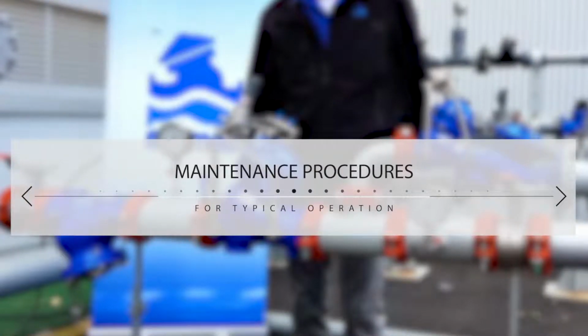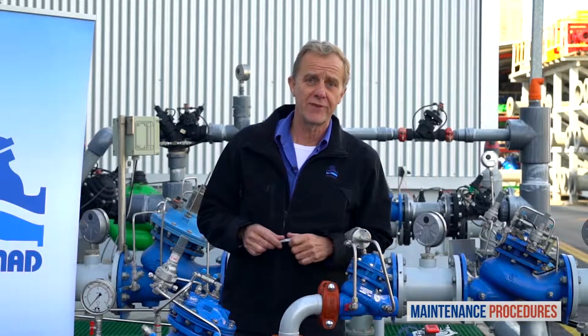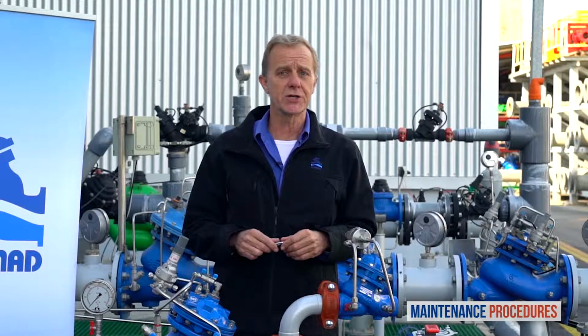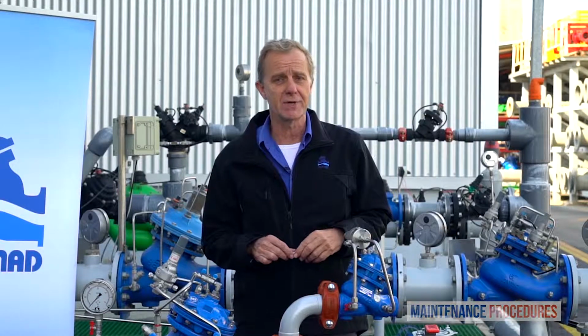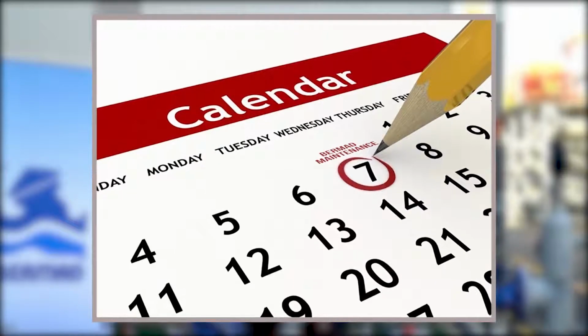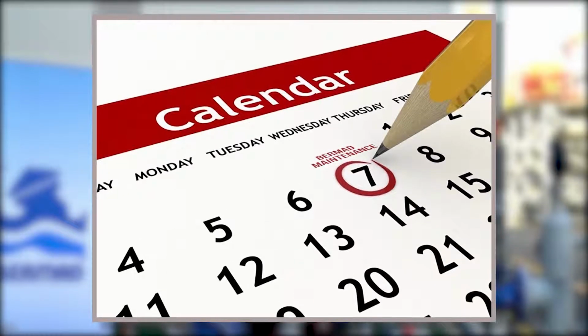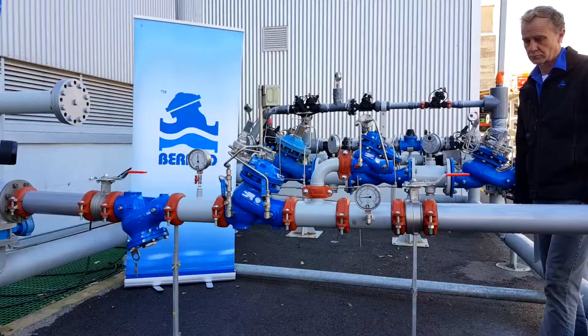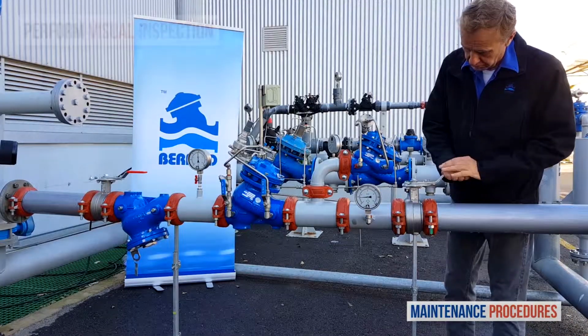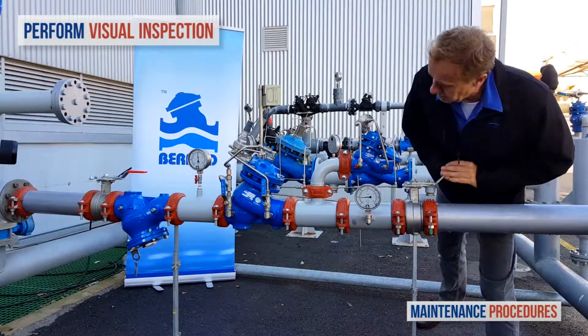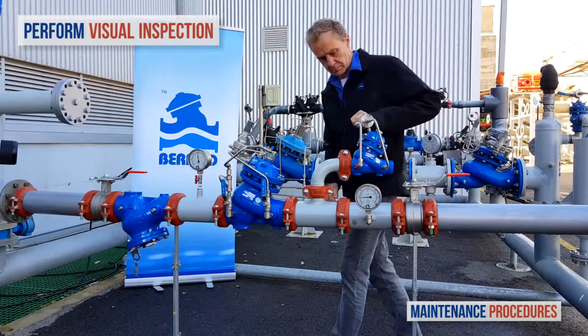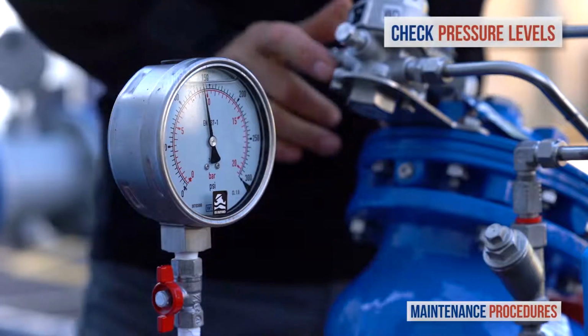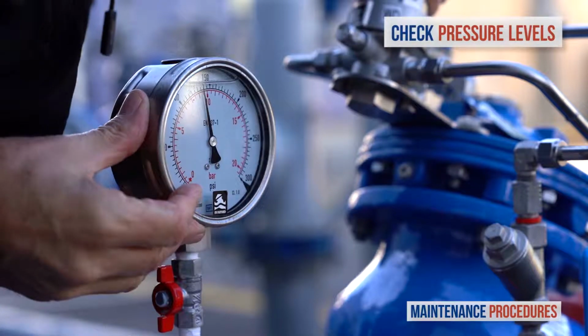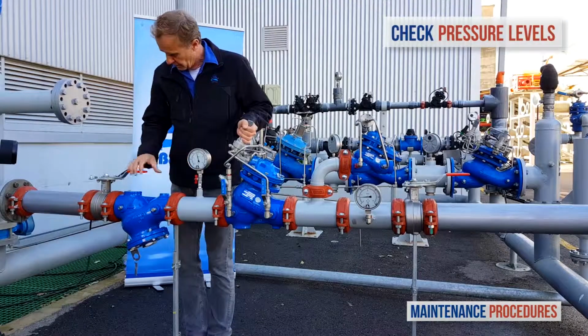Now let's discuss maintenance procedures for the Bermad PRV pressure reducing station with the relief valve. Note that your schedule for preventative maintenance depends on the actual conditions of use and the station's environment. Here we discuss a schedule suited to a valve operating under average conditions. On a weekly basis, perform a visual inspection of the station and check for leaks or external damage.